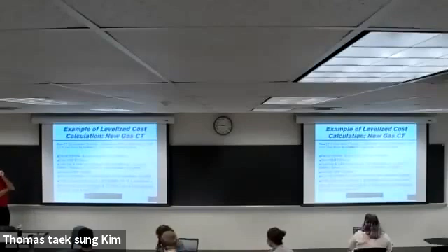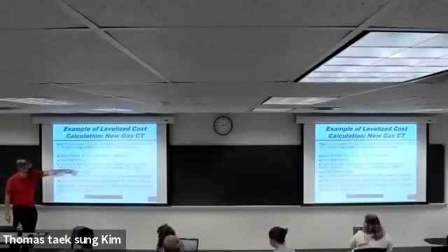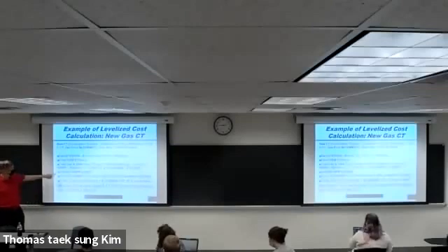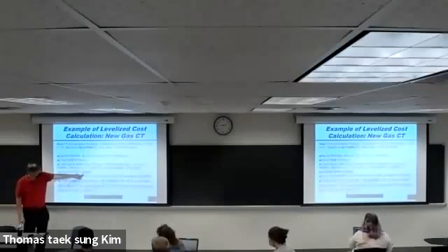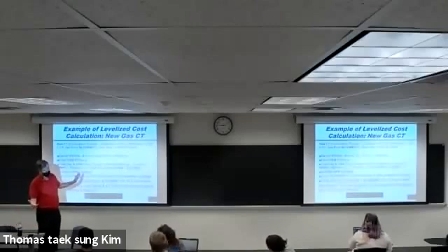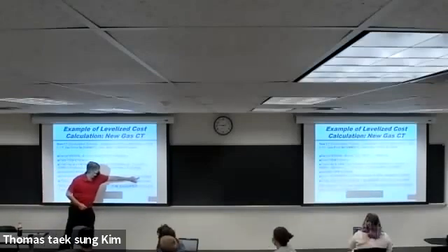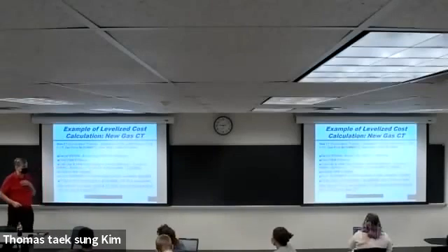It's all because of the capacity factor, right? You're spreading all those fixed costs, that capital and that fixed O&M, over a lot less hours, like an order of magnitude less hours, basically. Okay, so that's why you get a much higher cost. Variable O&M is only $2. Fuel $3 times 10,000. Nice easy math here. Keeping the heat rate at 10,000. So it works out to $30 a megawatt hour.